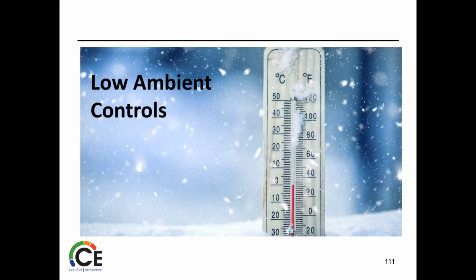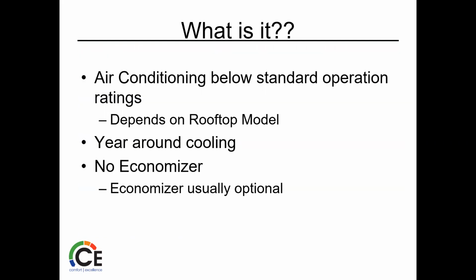All right, so rooftops at times, depending on the application, need some low ambient controls. Especially, again, if we want to operate air conditioning below the standard operation ratings of 60 to 70 degrees, right? Depends on the rooftop model. It gives them year-round cooling if they want it. Economizer is optional. Just depends on what's going on through that.